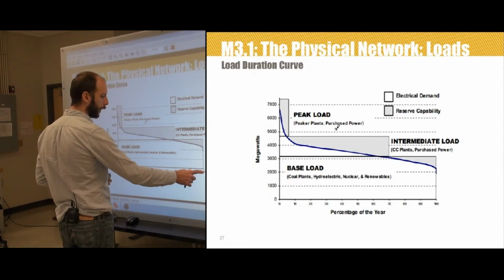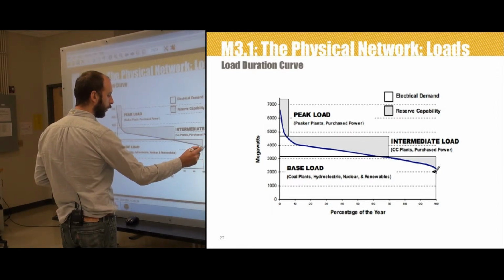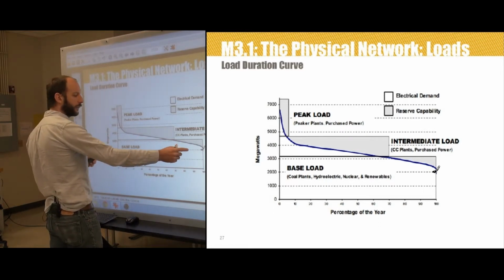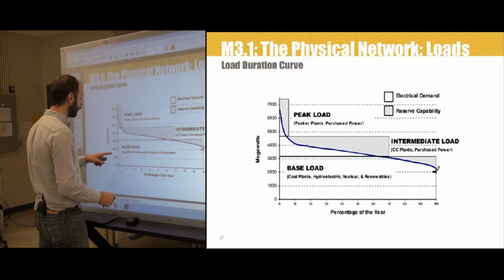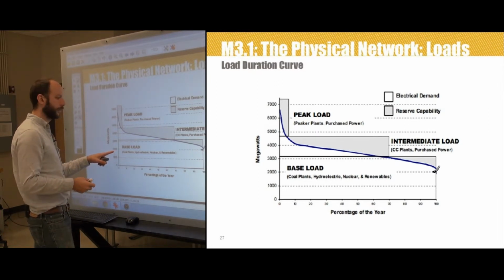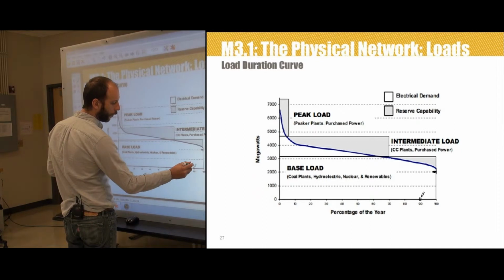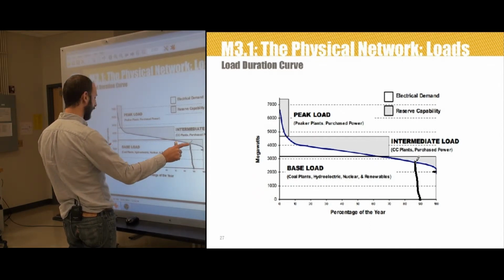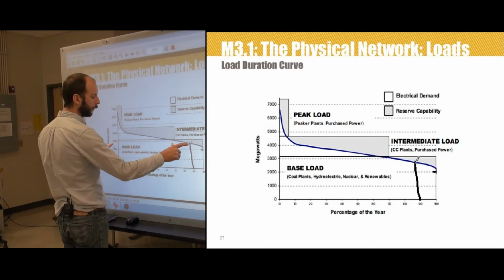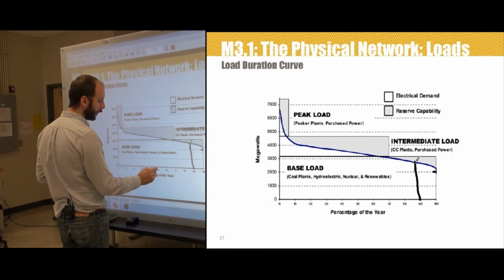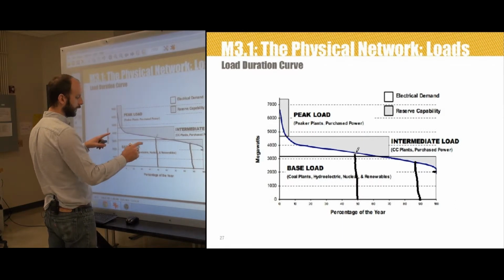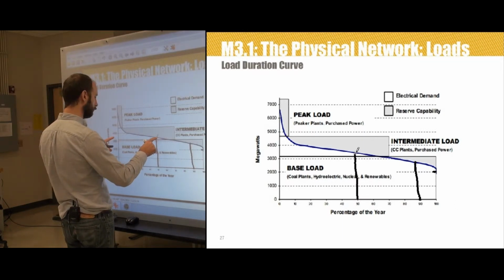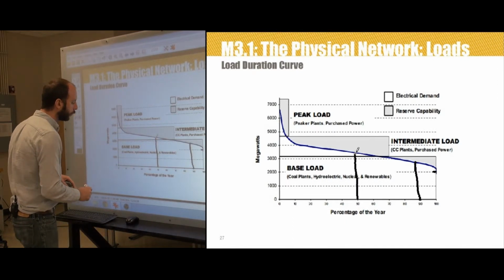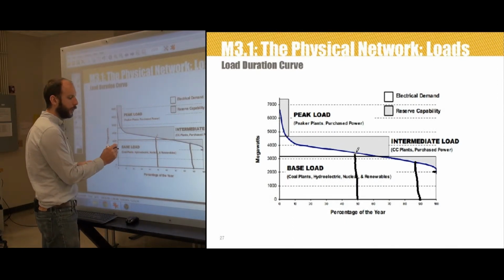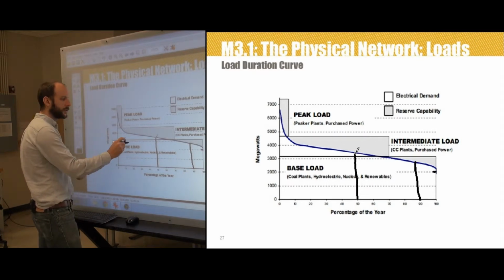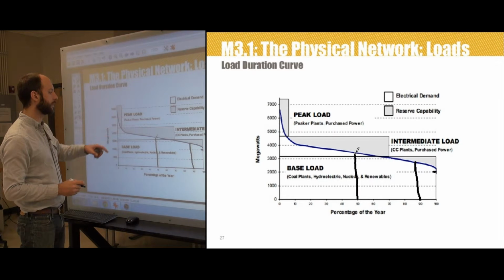So from this plot, I come over here and I see that the demand for whatever aggregate system we're representing really never drops below 2,000 megawatts. For 90% of the year, it's at 3,000 megawatts or above. So for most of the time, it's at 3,000 megawatts or above. For half the year, it's at 3,500 megawatts or above. And we can start seeing what we consider base, what we consider intermediate, and what we consider peak.